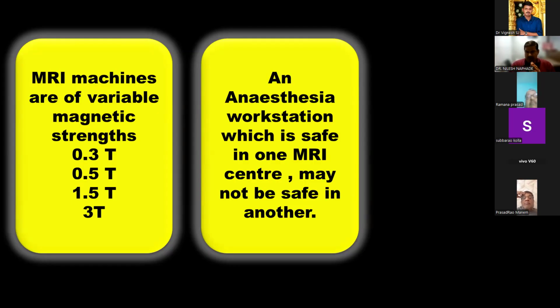This can happen if you switch machines between centers, or in a medical college, where there is an MRI center and the anesthesia machine is bad, not working, the workstation is out of order. So you say sometimes we will bring that machine from the operation theater. It is MRI safe, they had told me when I purchased. But you don't know whether it is suitable for 3 Tesla or only for 0.3 Tesla. If it is suitable for 0.3 Tesla, it is suitable for a weak magnet. If it is brought into an MRI room with a 3 Tesla MRI machine, the 3 Tesla is a very powerful magnet. It will suck that machine.